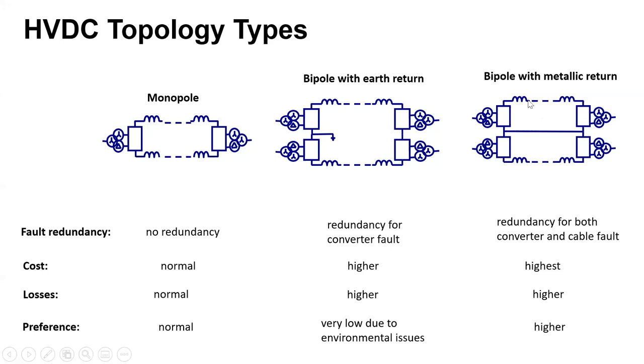So the fault could be in this converter, or this converter, or a transmission line, and that will mean only this circuit going out of service, not this circuit. And with this circuit, half of the rated power can still be transmitted between ends.